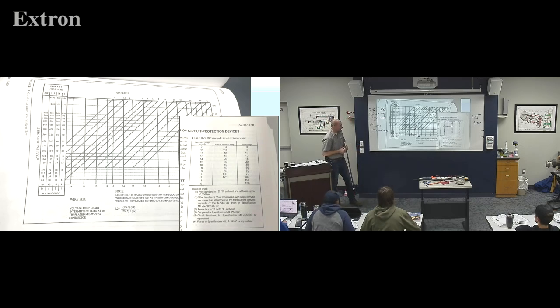If I just go install that in my aircraft, I go, oh shoot, I need a circuit breaker to protect my wire, right? Let me come over here to 18 gauge wire. What size circuit breaker do I need to protect my wire? Oh, a 10. I can't put anything bigger than a 10 to protect my wire. It's not protecting it anymore. So if I put a 10 amp breaker on this circuit, what happens when I turn my light bulb on? Pop. That won't work. Shoot. Well, what if I put a 20 amp breaker in? Well, now I'm illegal because my breaker's too big for my wire according to the chart.